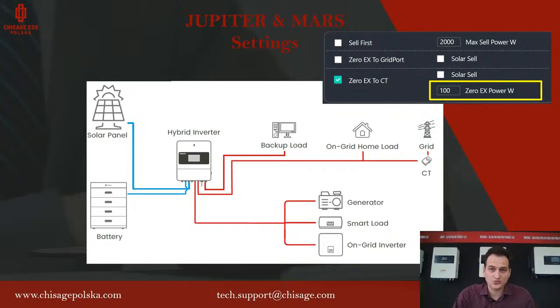To pick this option, we have to pick CT or meter. If we have none picked in our grid settings, we cannot choose this option. So if you cannot choose this option in any installation, just check if you picked CT or meter, because if you don't have either of these, you cannot check this option. That means the inverter will stop power on the CT, so we'll try to have zero on the CT measurement. So we'll secure the backup load, we'll charge the battery, we'll also secure the on-grid home load.